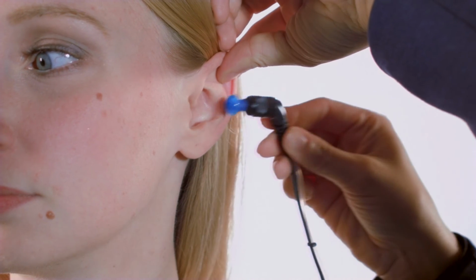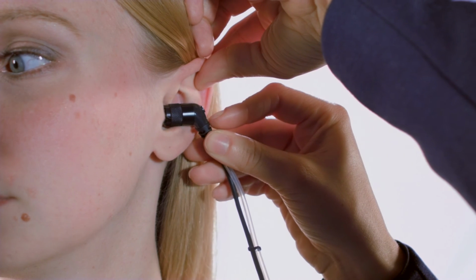The probe also needs to be inserted in the test ear. The probe and phones should be placed far enough into the canal so that the probe will stay in place on its own without the tester holding it in place.